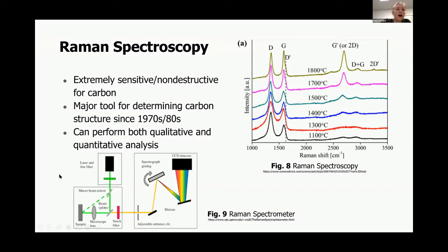So this is a general layout, sorry, the image is kind of blurry, of the instrumentation of a Raman spectrometer. So first you're going to have a laser source or a light source, and then it's going to split here. It's going to hit your sample to excite some of these specimens' electrons. And then the Raman effect differentiates different scatterings of light. So then this filter here is going to collect the Raman scattered light, and then it's going to filter out all the other light, like the anti-Stokes light and the Rayleigh light.